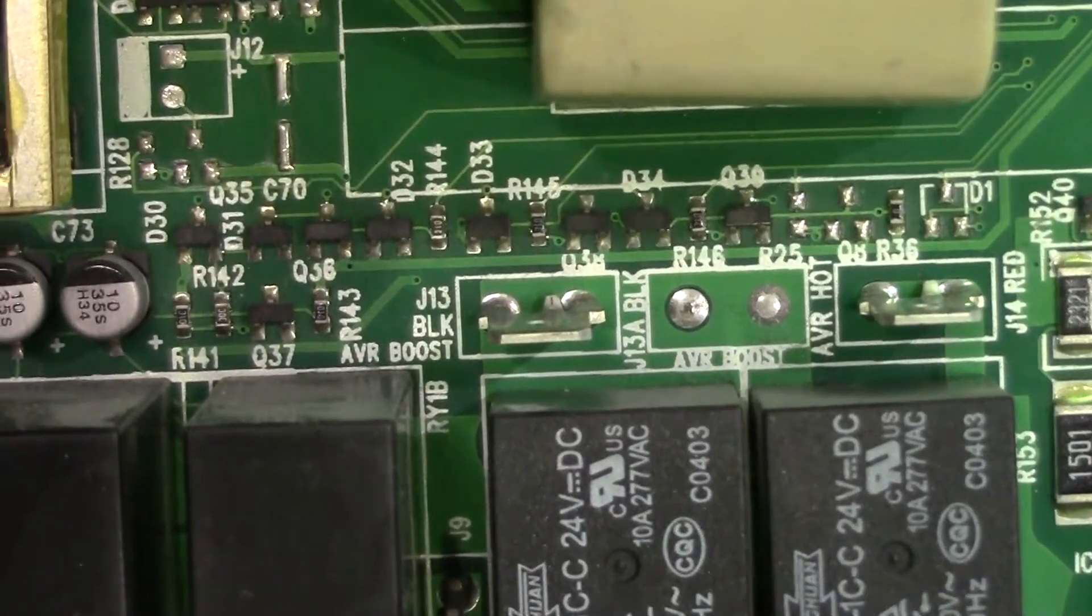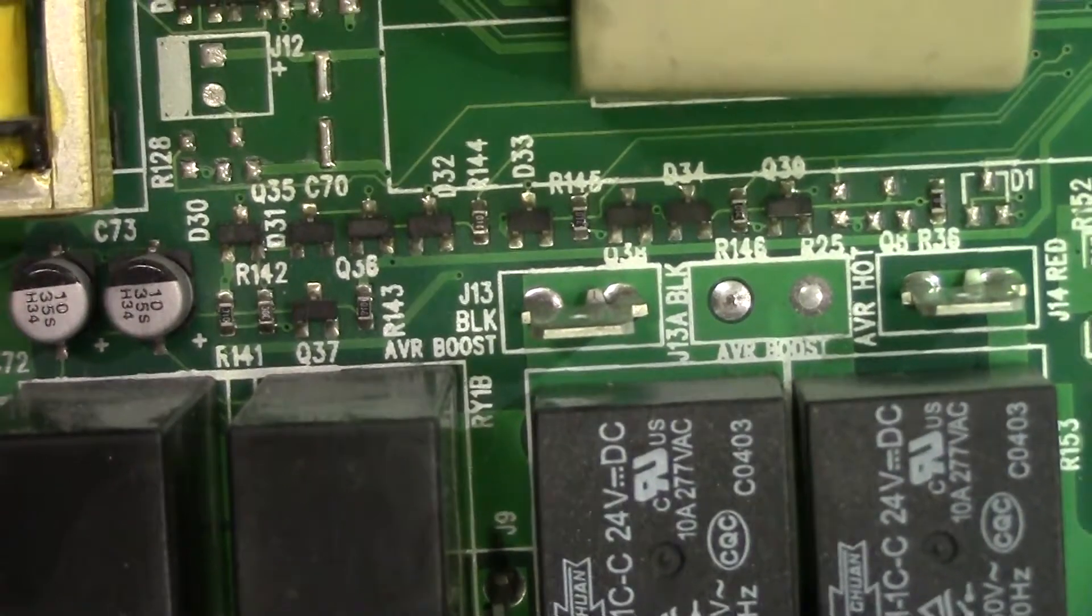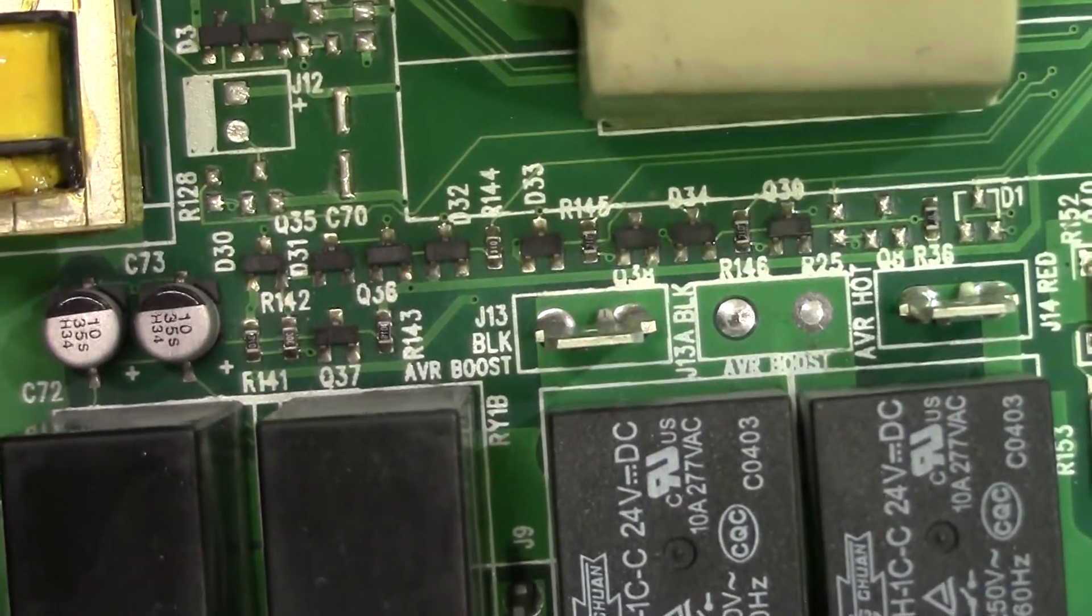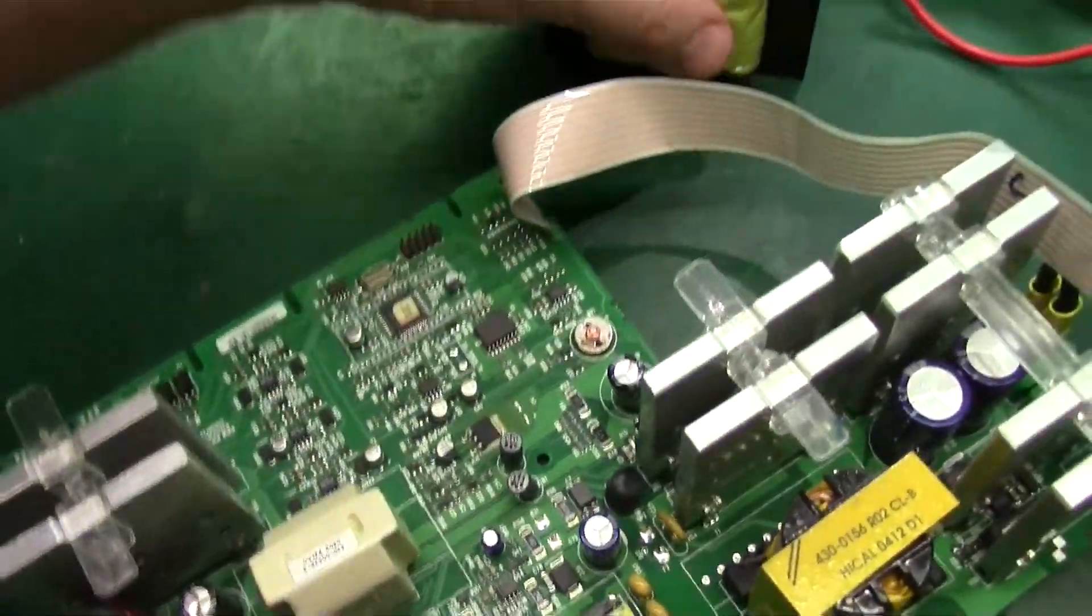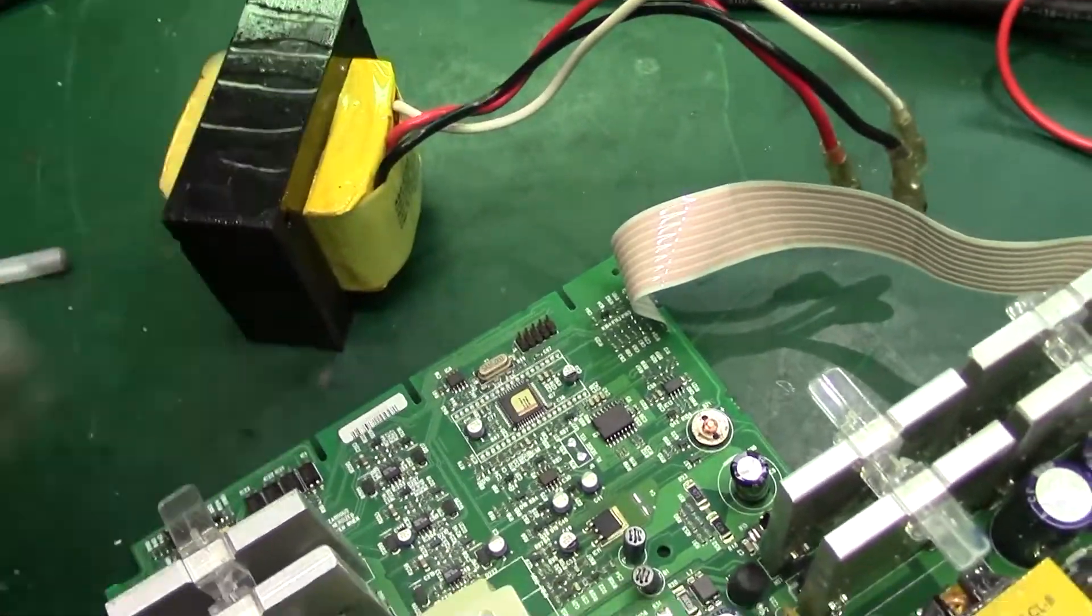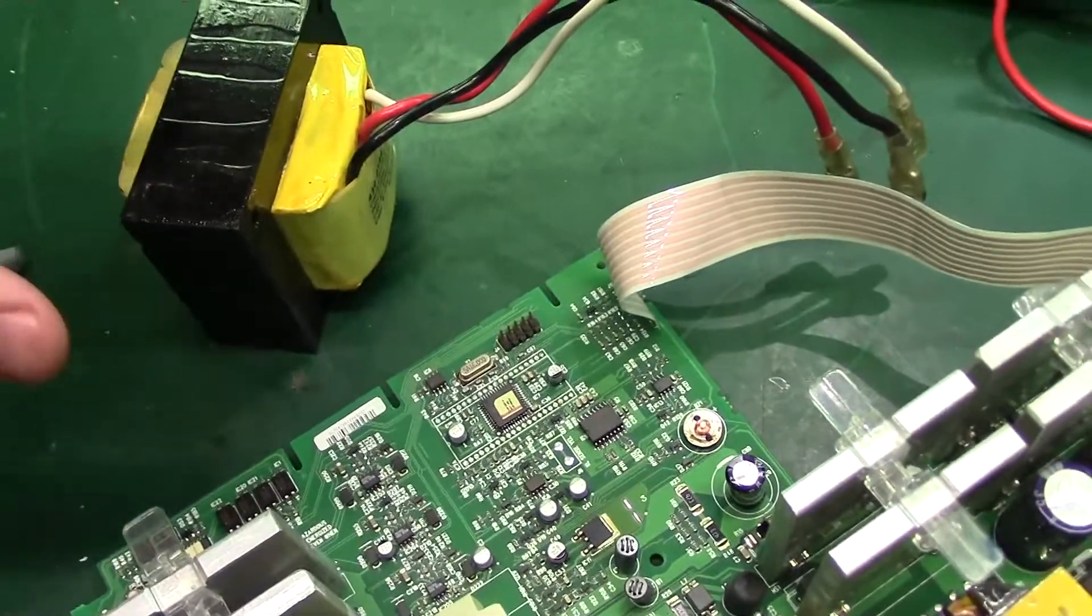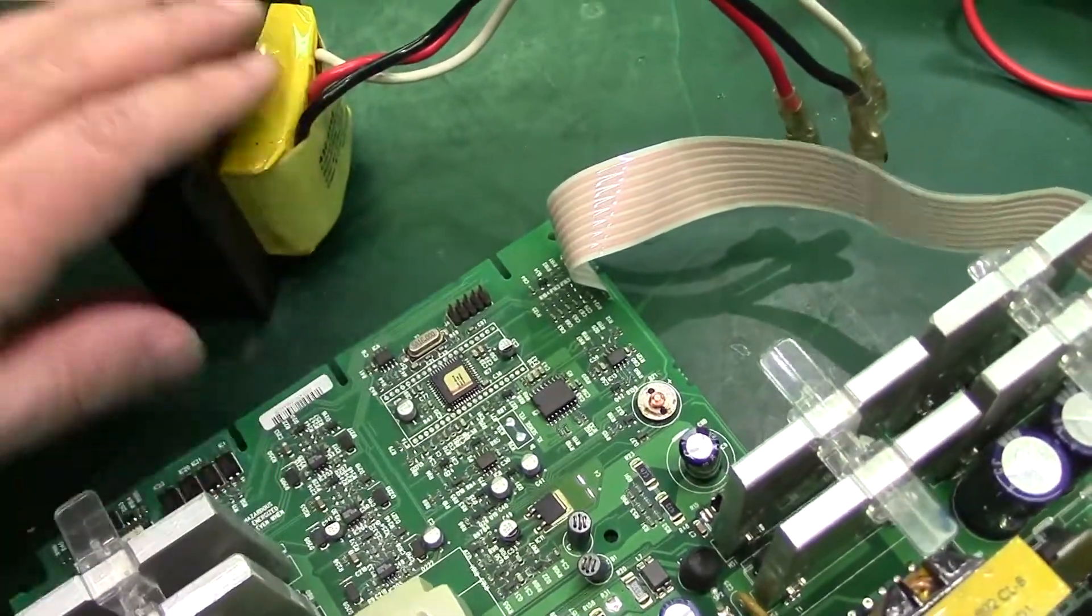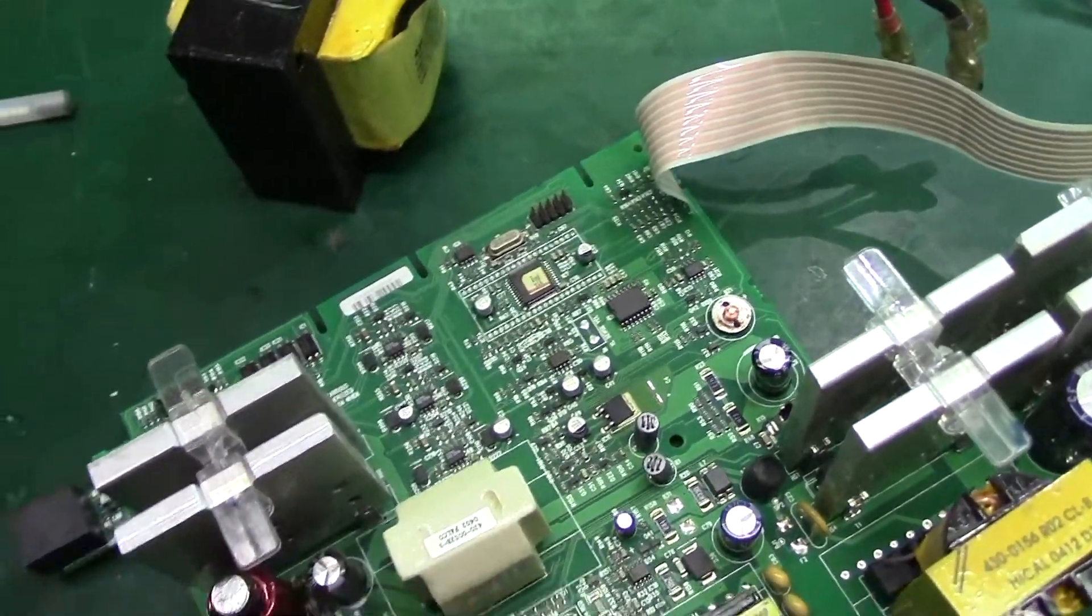Shaky vision, but if we look closely at the relay, you can see that they are labeled AVR boost. AVR boost is a feature that these UPSs have. When the line voltage starts to dip, they will actually run power through this external transformer to actually step up the line voltage a little bit. I think it's a bit more complicated than that, but they use these external transformers to actually adjust the line voltage.